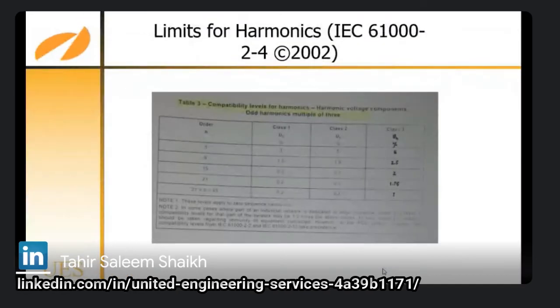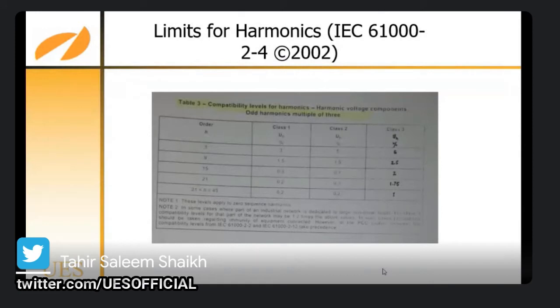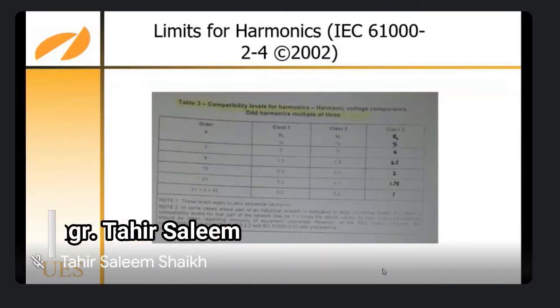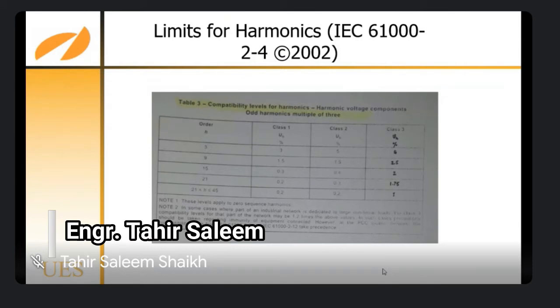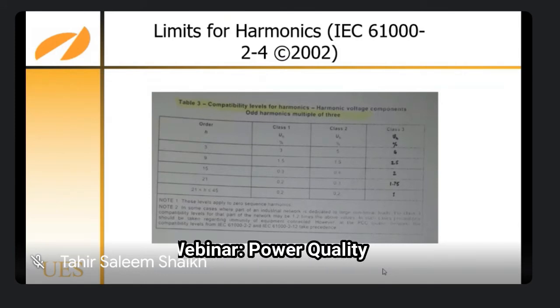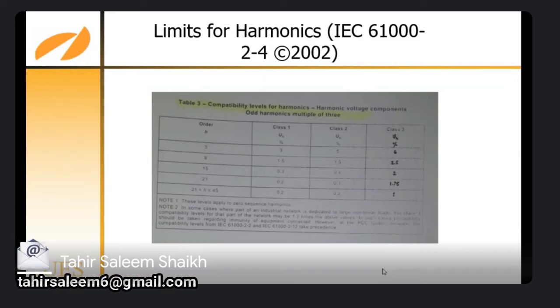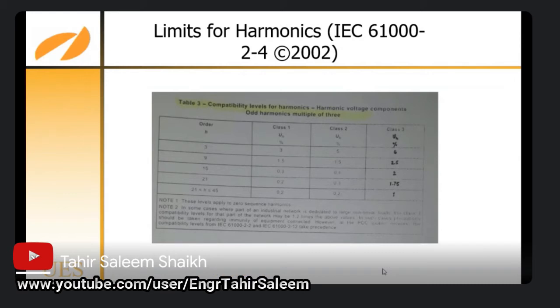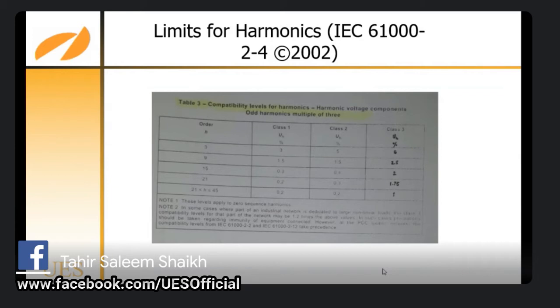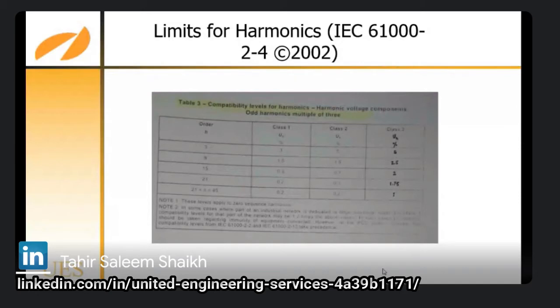that you can see over here. Generally, the harmonic limitations, the dangerous harmonics are the odd harmonics. Even harmonics don't play any role in the problems. So that's why class 1, 2, and class 3 limitations are specified over here. Class 1 it is 3%. If I read it out, it's 5% class 2, and class 3 it is 6%. So if you are using an environment where the electronic sensitive equipment are very much, then you have to restrict yourself to 3%. So these are the different classifications over here.